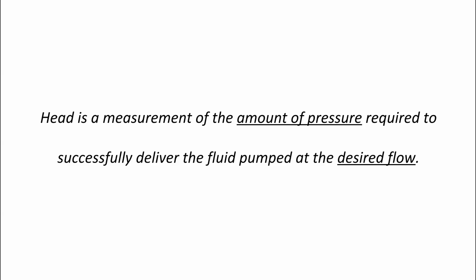The amount of pressure would be whatever pressure is needed. For a home you may need somewhere between 40 to 60 psi. If you're filling a reservoir, you're not going to need any pressure at all - you're just looking to get the water in the tank. In most sewage applications where solids handling is involved, there's not necessarily a requirement for pressure. But in effluent sewers and on-site sewer systems where you may have a pressurized drain field, you're going to be looking at requirements that involve pressure.